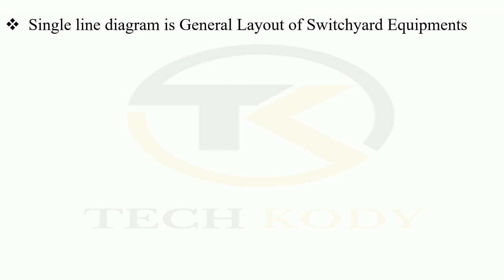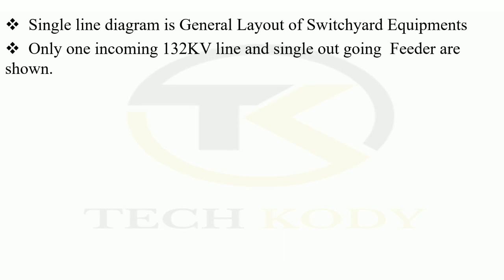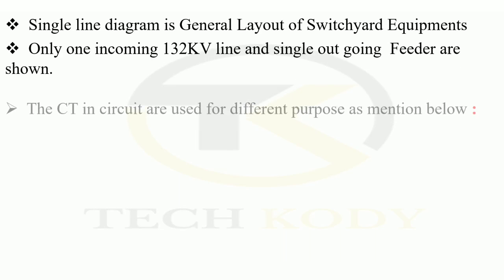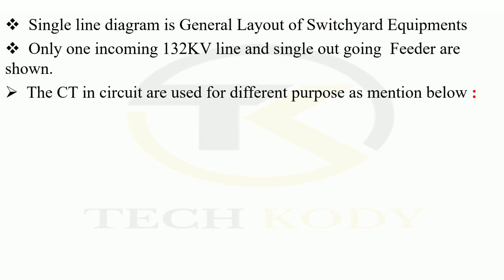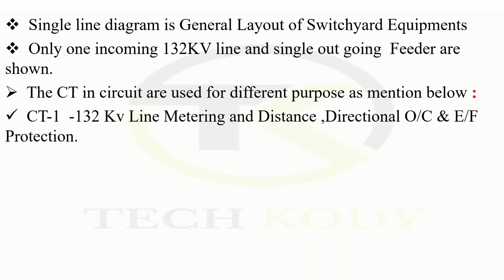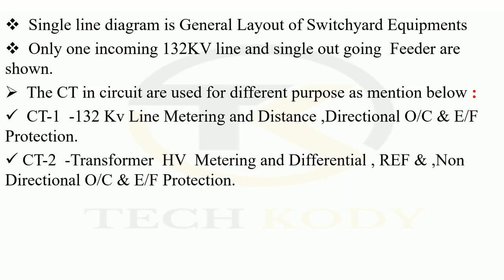The single line diagram is generally a layout of switchyard equipment. Only one incoming 132 kV line and single outgoing feeder are shown. The CT in the circuit is used for different purposes: CT1 for 132 kV line metering and distance directional overcurrent and earth fault protection. CT2 for transformer HV metering, differential, restricted earth fault and non-directional overcurrent earth fault protection.